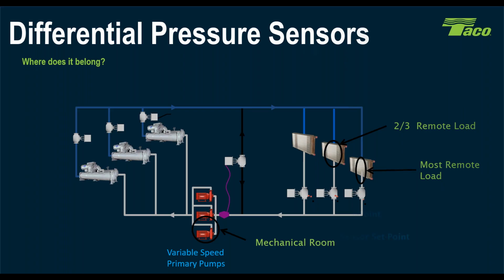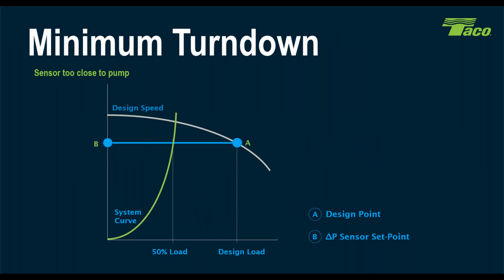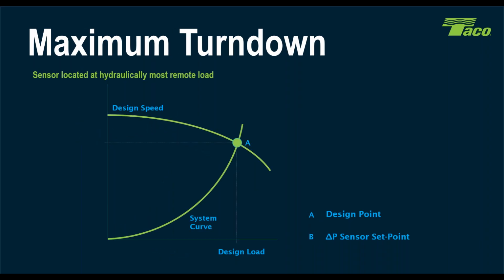It's virtually worthless. Yep. So what happens is I get this really narrow turn down band. So I don't get all the benefit of having a pump that'll go from 100% down to 30%. So if I put the sensor out, and the further I move away from the pump, what ends up happening is, so same design point, and we're going to go through the same kind of scenario here. Okay, as soon as I get my cursor back where I want it.